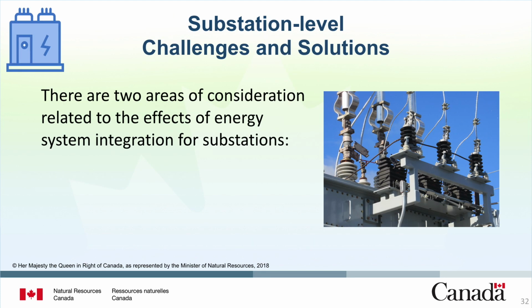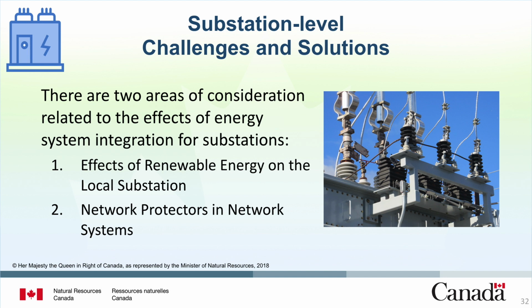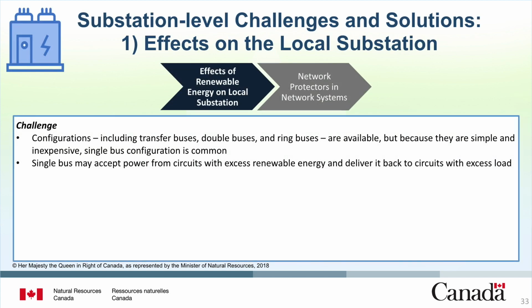There are two areas of consideration related to the effects of energy system integration for substations: local effects and network protectors. We begin by discussing the effects of renewable energy on the local substation. The challenge is that an electrical substation consists of a transformer by which voltage is converted from transmission to distribution voltage, as well as a bus with circuit breakers, current transducers, and isolating switches on each circuit coming off the bus. Configurations, including transfer buses, double buses, and ring buses, are available, but because they are simple and inexpensive, single bus configuration is common. This single bus may serve to accept power from circuits with excess renewable energy and deliver it back out to the circuits with excess load.